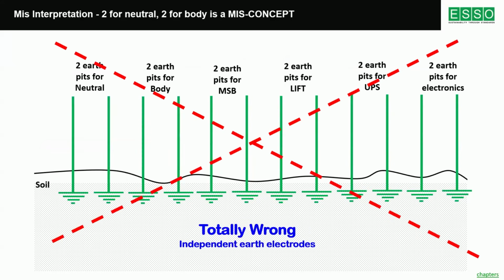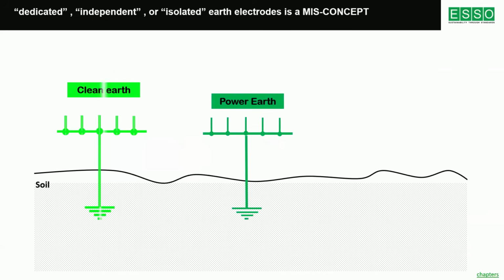Separate earth pit for different electrical items, such as 2 earth pits for neutral of a transformer, neutral of a DG, neutral of UPS, 2 separate for body, 2 separate for main distribution board, lift, and all. This is absolutely illogical, and this is totally against the concept of electrical safety. Unfortunately, even today, a lot of hospitals made even in the 21st century go behind this non-standard method, which is actually creating disaster, and it can create disaster in the hospitals in future.